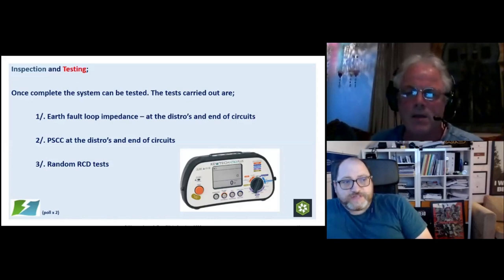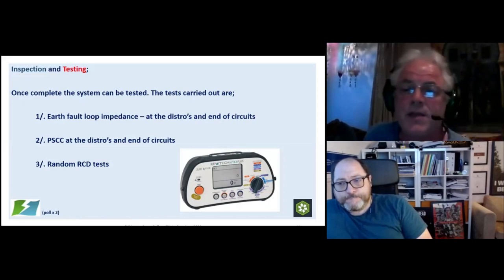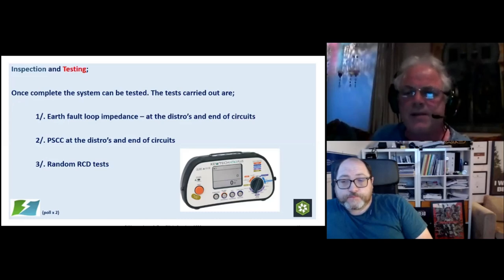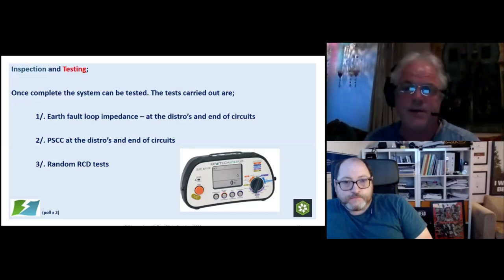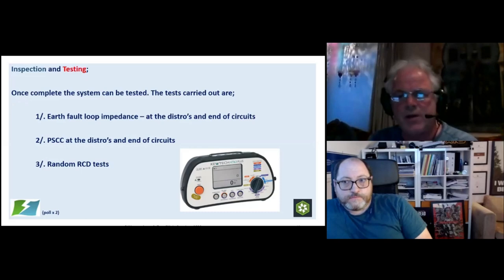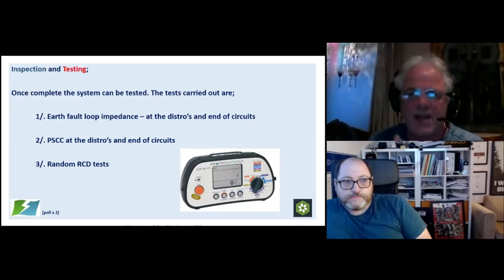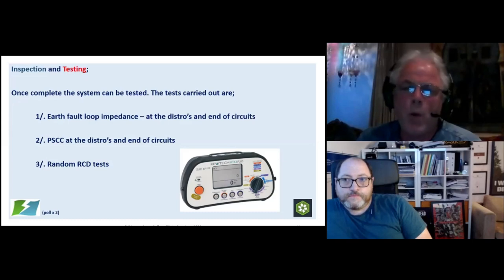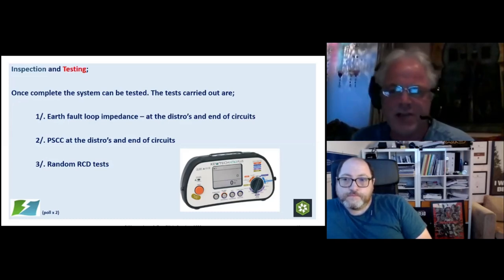Are there additional tests for distros with RCBOs? Again, it's one of these things that once we've set the RCBOs up, if they are adjustable or selectable, you should really test them to make sure they are operating at the right level. So yes, we will test the distros. I tend to test the distros for selectable RCDs, and that's mainly because I'm always mindful of the fact that I might not have got the selection right.